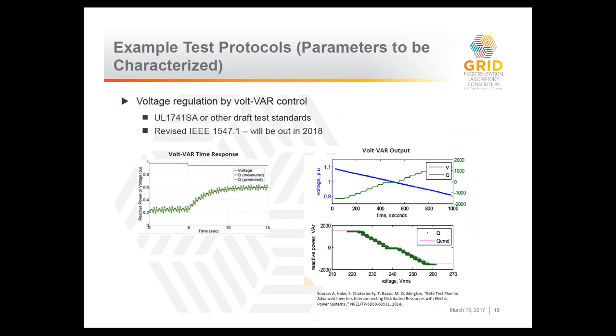This is an example of a voltage regulation function by volt-var control. Basically, you are measuring the terminal voltage, and based on that voltage, you are injecting or absorbing reactive power. The first one on the left side shows the time response: suppose there is a change in your voltage, how fast can your reactive power respond? As you can see, this one shows a first order response. Based on our experience testing probably 10 to 15 different types of inverters, we saw a variety of responses, for example ramp type or first order. We even saw second order in some inverters, where it overshoots and then settles down to a value.